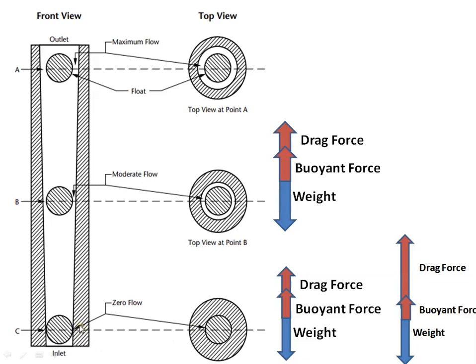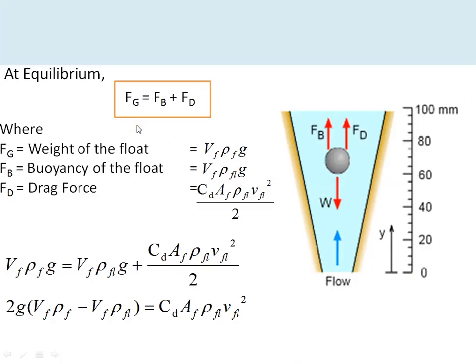When there is an increase in flow rate, it disturbs the equilibrium. The increase in flow rate increases the drag force, which moves the float upward — since the upward forces now dominate — until it settles at a new position where the upward and downward forces are again in equilibrium. At equilibrium, buoyancy force plus drag force equals the gravitational force, i.e., the weight of the float.